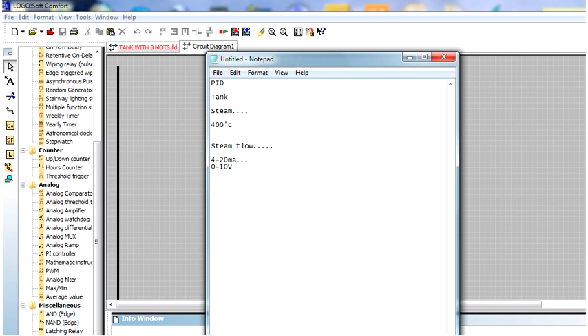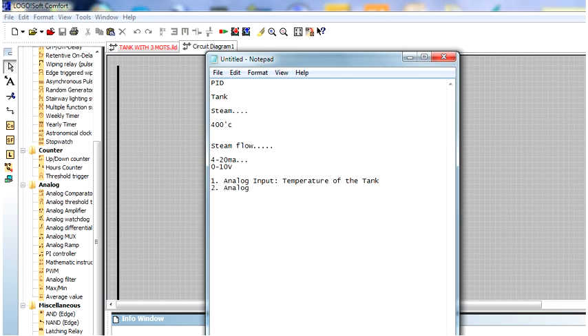Now come to the point. We have two analog signals: one analog input and one analog output. The analog input is the temperature of the tank, which we can read with a temperature sensor. The analog output is the steam flow valve. My requirement is to keep the temperature of the tank at 400 degrees, so the target is to control the steam flow valve in the right way to maintain that temperature.